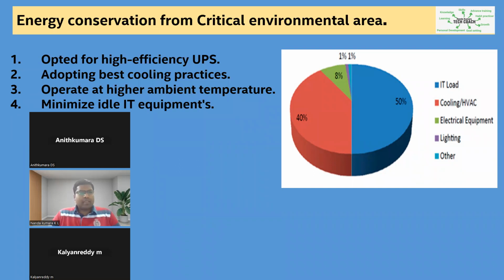The second option is best cooling practices. There is 40% energy consumption from the cooling system. Again, I'll not talk about the chiller side, that is a different part. I'll talk only about the inside of labs and data centers. What are the best cooling practices? First, hot and cold aisle containment enclosure configuration, which is one of the important best practices. If we have properly segregated cold and hot aisle containment, you will save at least 15% of energy from the cooling side.